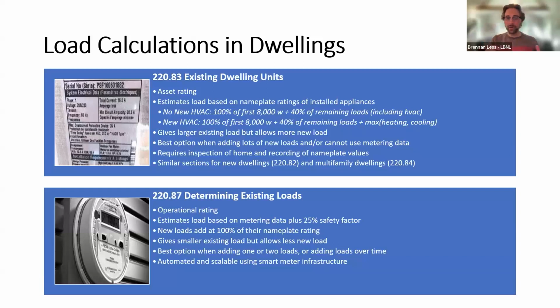It does require that you go around and inspect and record all the nameplate values in the home, so it's kind of burdensome in that way. And we'll highlight that there are very similar corresponding sections for new dwellings in 220.82 — those are used in almost all new housing development calculations — and in multifamily dwellings in 220.84.